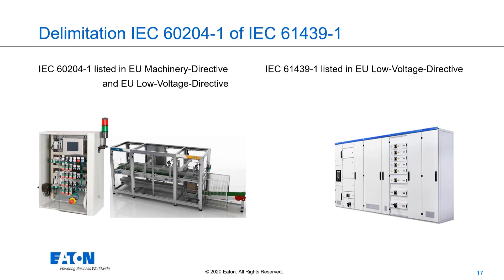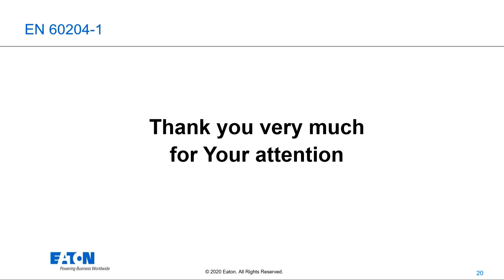Regarding the delimitation between IEC 60204-1 and IEC 61439-1: IEC 60204-1 is listed in both the European Machinery Directive and the European Low Voltage Directive, while IEC 61439-1 is only listed in the Low Voltage Directive. Therefore, for all parts related to machinery, IEC 60204-1 must be used. Thank you very much for your attention.